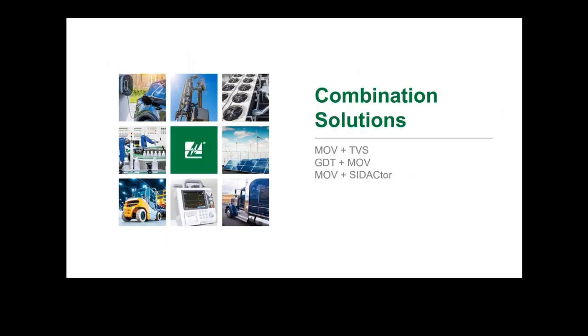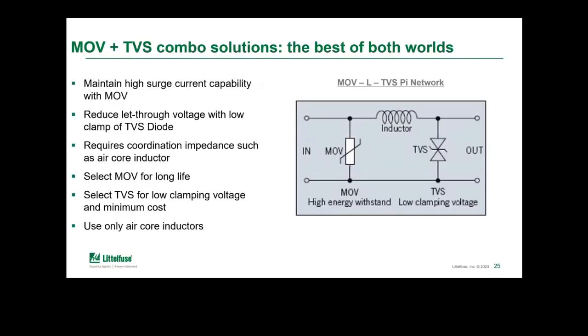So the next thing I'm talking about is some combinations. The first combination I want to talk about is that of an MOV with a TVS diode. As I mentioned, TVSs have very low clamping voltage, whereas MOVs have higher clamping voltage, but MOVs are much higher energy. By using the two in combination, you can improve the let-through performance while still maintaining high surge capability. And they're typically used in what's called a pi network.